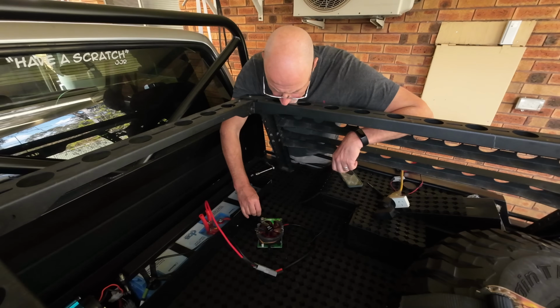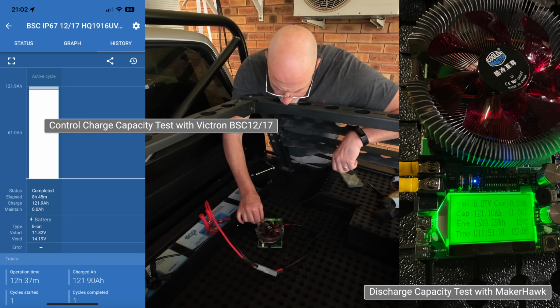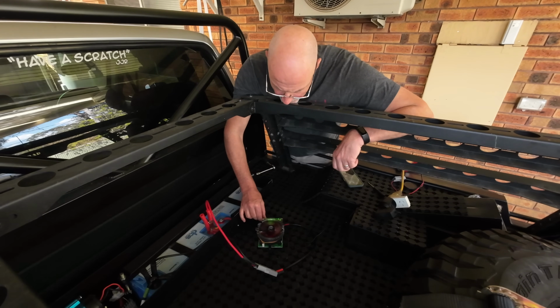I recently also did a capacity test on 2 130 amp hour DCS batteries which I had in storage for over a year. One was close to capacity, but the other lost 6.23%, or maybe it never had the full capacity. Unfortunately, I didn't do an initial capacity test.